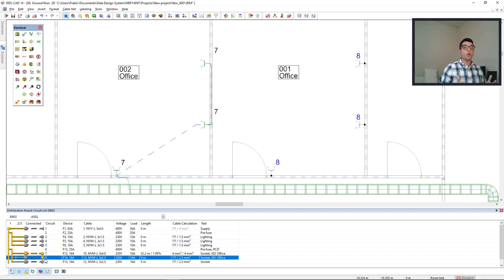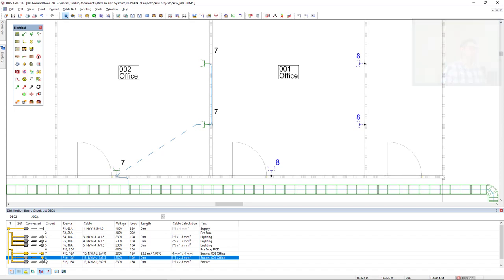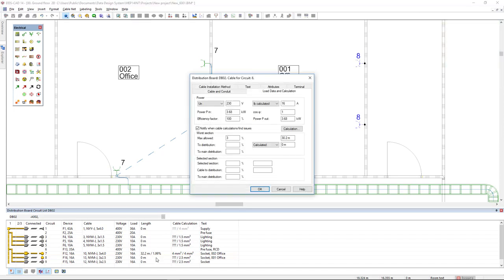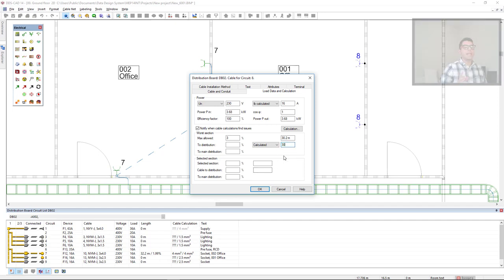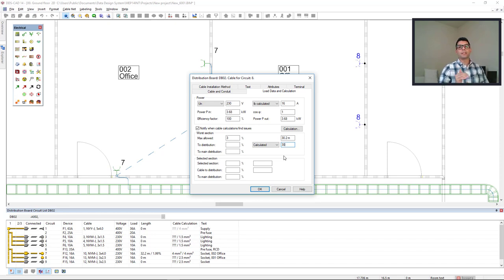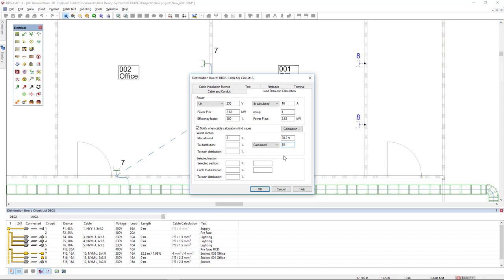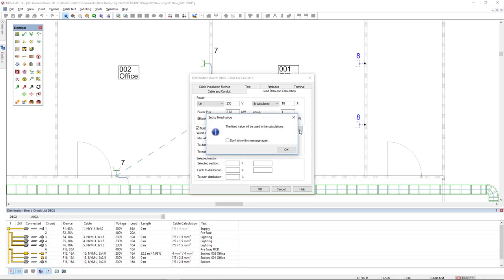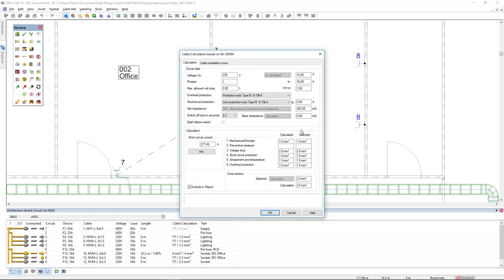How could we then calculate the cable? We would have to come to the length column and manually insert the cable length. And I will insert this length slightly below the limit for the voltage loss, indicated by 30.2 meters. And I will directly click in the calculation button. We see that DDS CAD will fix the value, that the fixed value will be used in the calculation. And we see that all the values here are within the calculated results.